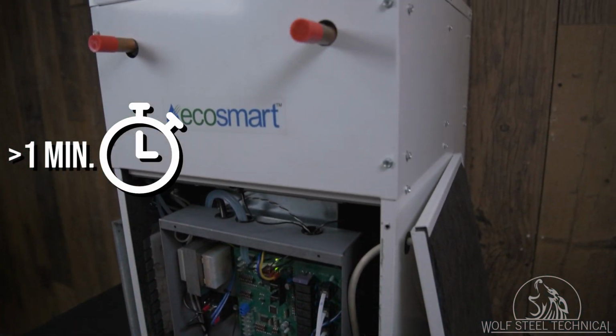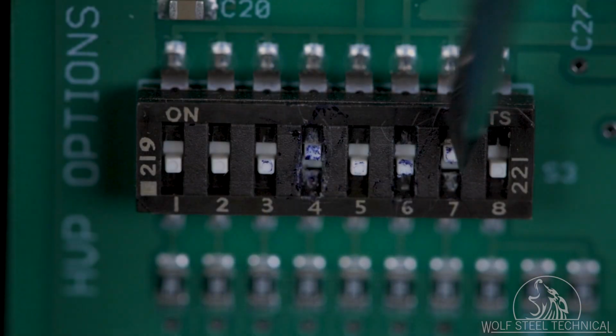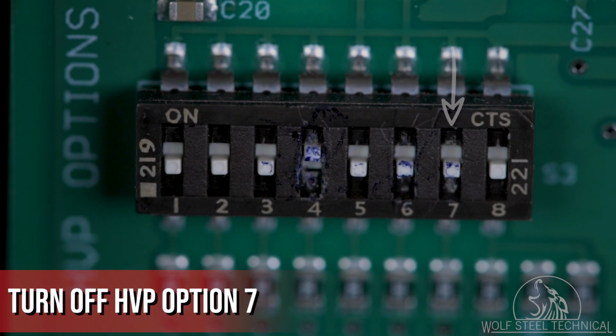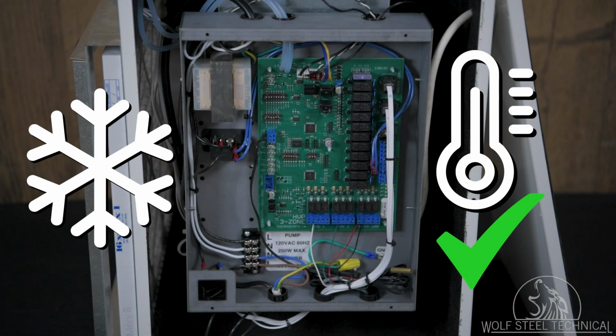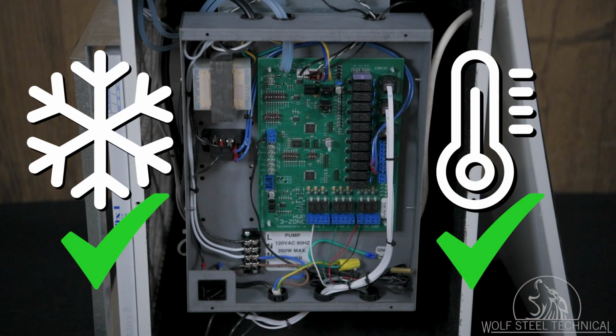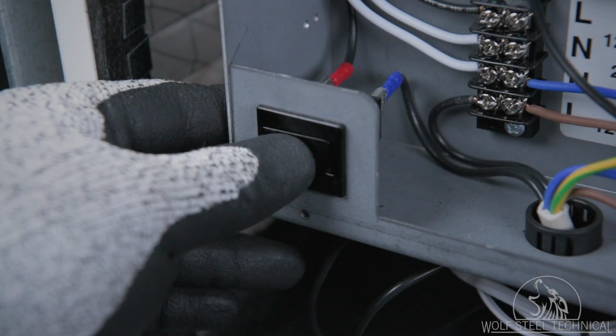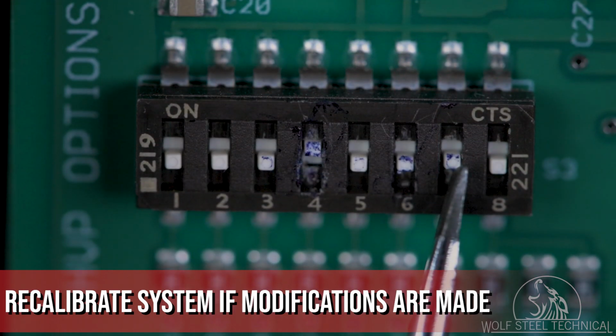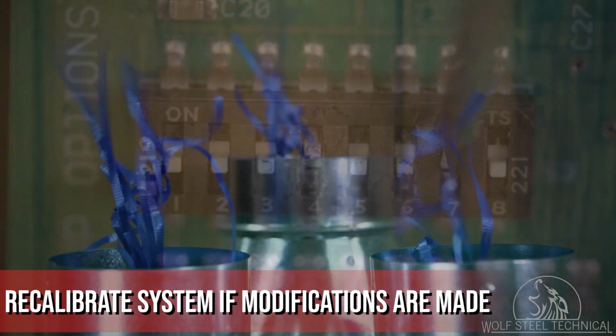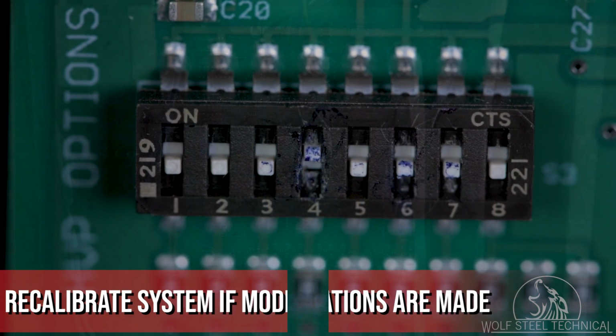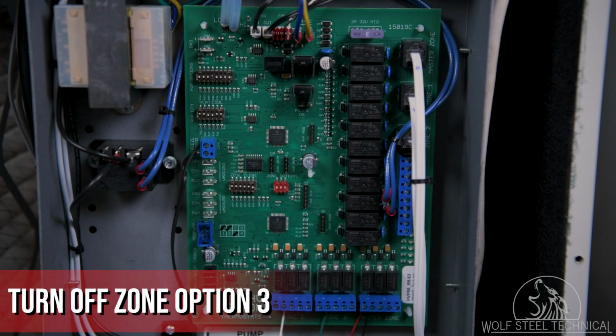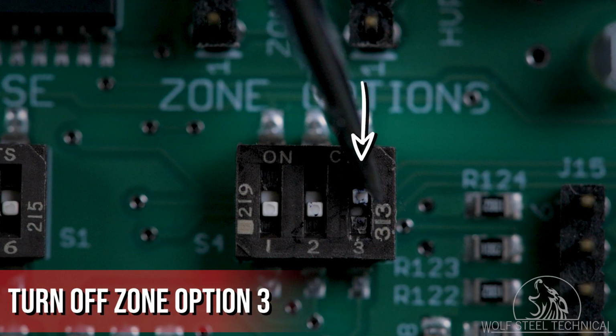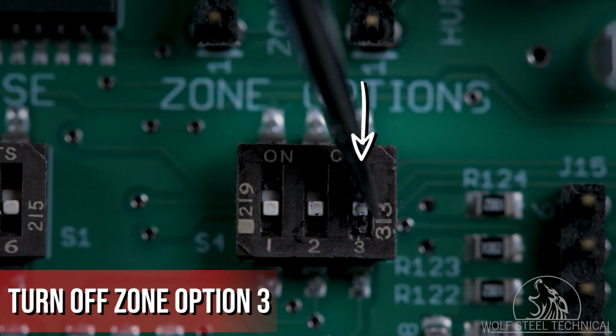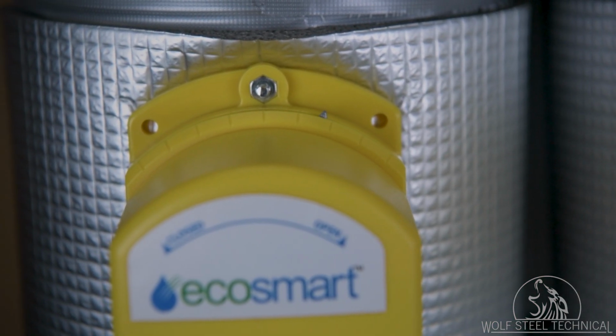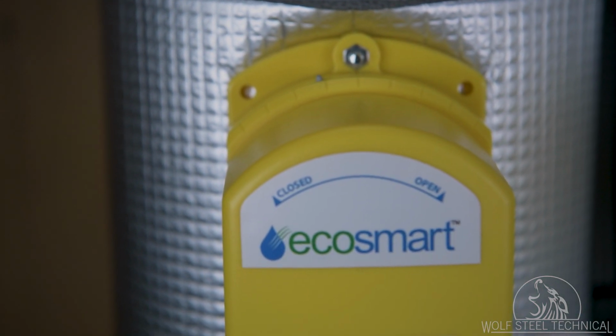Once again, allow the system to run for at least 1 minute, then set HVP option 7 to the off position. The cooling calibration parameter is now permanently stored in the controller and will be retained even in the case of a power loss. Once again, if any modifications are made to the system, the calibration must be repeated to ensure correct operation. Now, turn your attention back to the zone option switches and ensure the zone 3 switch is set to the off position for normal operation. Then allow sufficient time for all dampers to close.